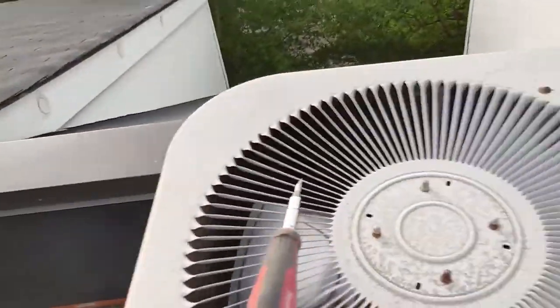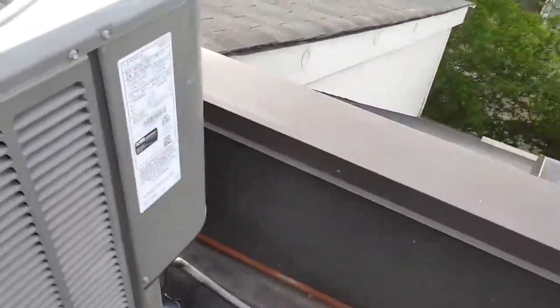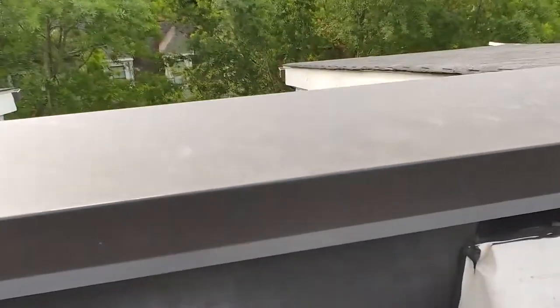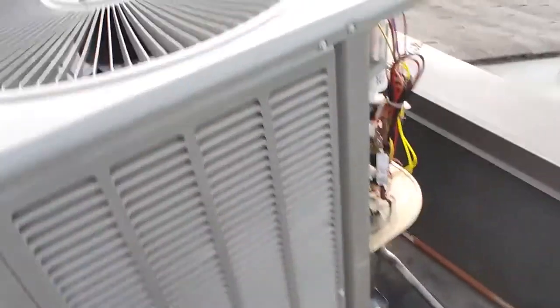I'm gonna call back here — it's supposed to be just a maintenance visit. A maintenance guy was out here, but the unit stopped running after he left. I'm taking a look to see what we got. We've got terminals — he forgot to put the terminals back on the capacitor. So hopefully he didn't cause any damage. I'm going to disconnect, check it out, and get that back on and reconnect these.